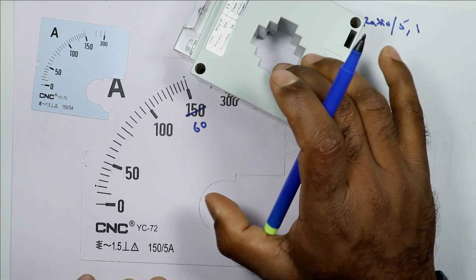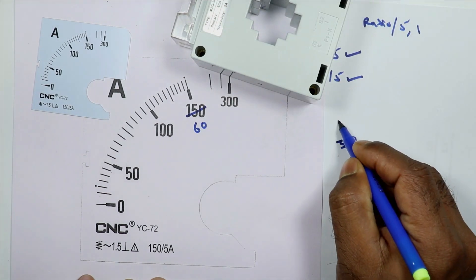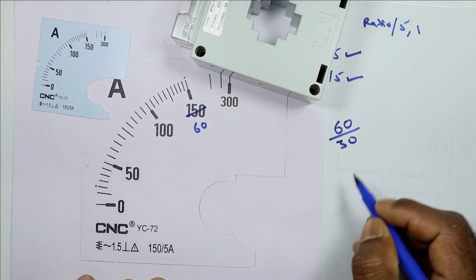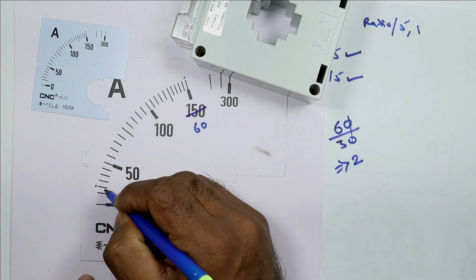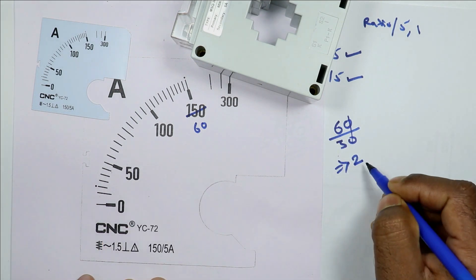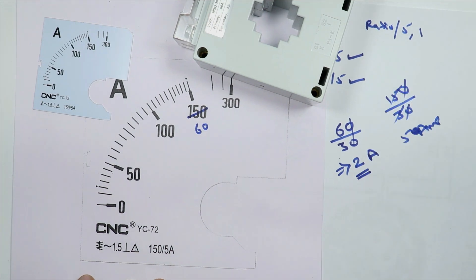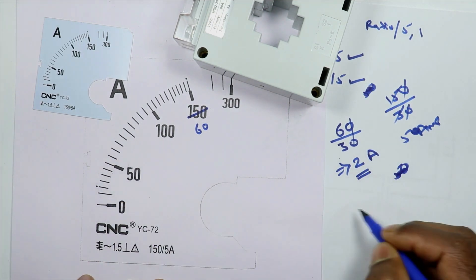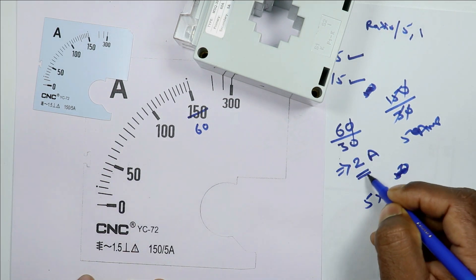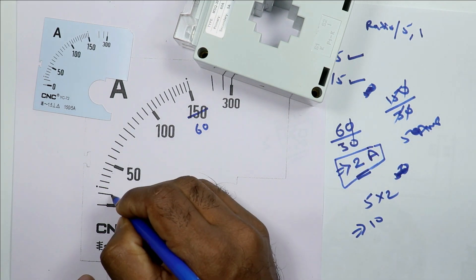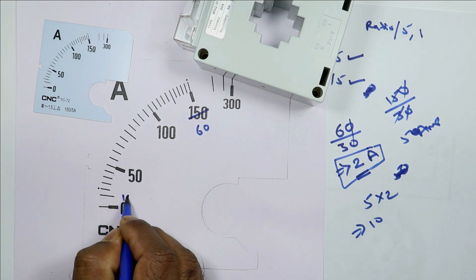The ratio of this CT is 60 by 5. I will write 60 divided by 30. On dividing the result will be 2. This means the difference between every two consecutive lines is 2 ampere. We have to do scaling as per 2 ampere. This medium line is used for counting of 5. I will multiply this by 2. I am multiplying this by 2 because one scaling is 2 ampere. So 5 into 2, 10. This line will become 10 ampere.